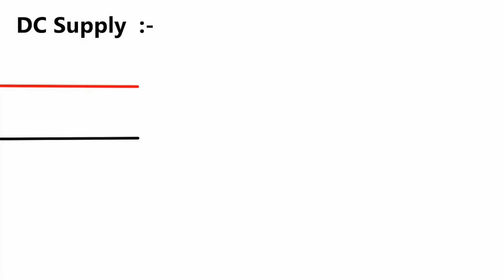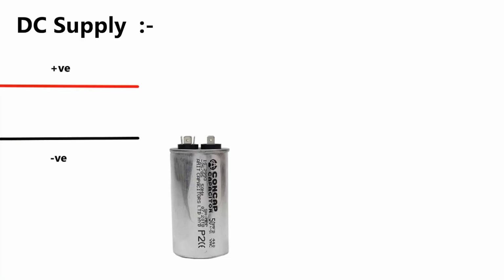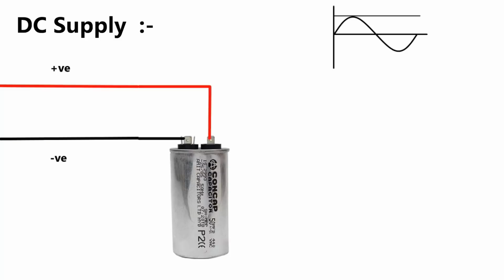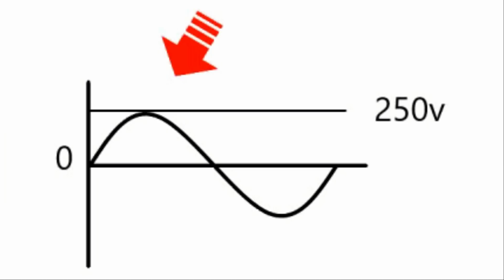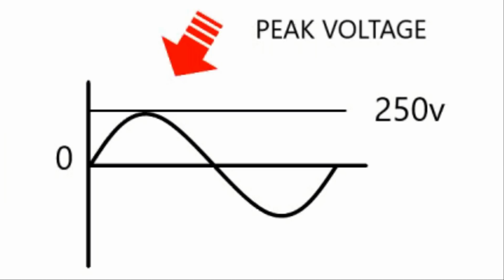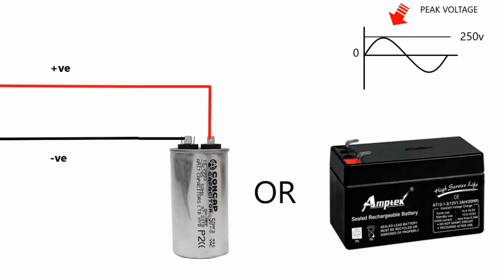But in DC measurement, especially when the power supply is connected to a capacitor or battery, the meter has no choice but to measure the voltage at which the capacitor or battery is charged, which is always the peak value, and peak value is always higher than the RMS value.